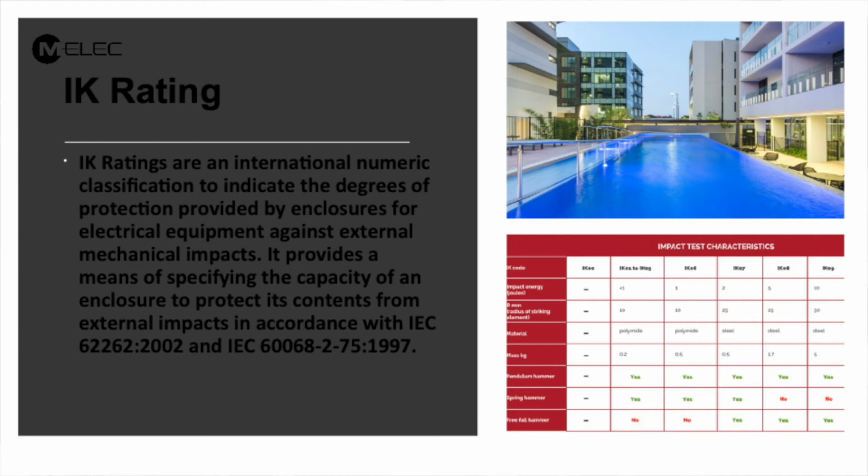The impact rating is determined by a series of tests, and however the light comes out is the impact rating that it gets. There are tests ranging from a swinging hammer, to dropping a designated weight onto a light fitting, to dropping the light fitting itself. All of these tests indicate the impact rating of that light.